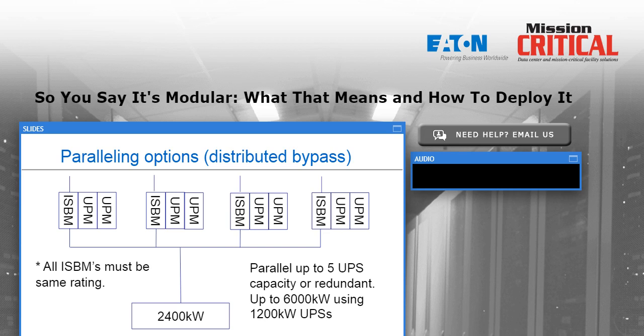Michael asks, can you parallel with three-phase, three-wire systems, or does everything need to be three-phase, four-wire? We and most of the other vendors can parallel with three-phase, three-wire or three-phase, four-wire. It is more common to parallel, especially at 480 volts, three-wire systems. But we, and most vendors, if not all of them, recommend that the upstream source be a grounded Y connection.